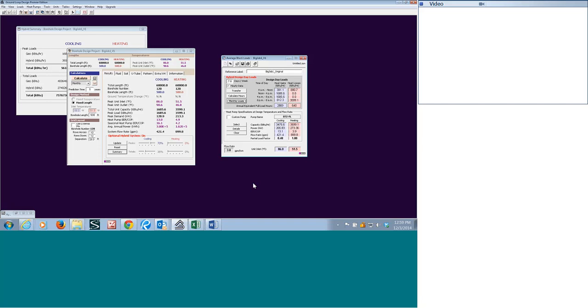Actually, what I'm finding is that, by definition, most commercial jobs are not going to be balanced. You're either going to be heating dominant or cooling dominant. And everyone makes this big ado of balancing the loads to have a perfectly balanced loop field so that you'll never have this theoretical heat creep or theoretical heat loss over the years. A good way to test this, Richard, is to pull out your cooling or your heating loads entirely and run your loop simulation. What you'll find is, if it's heating dominant and you pull out all the cooling load entirely and run it, in most cases the loop temperature in the first couple of years doesn't drop more than a couple degrees.